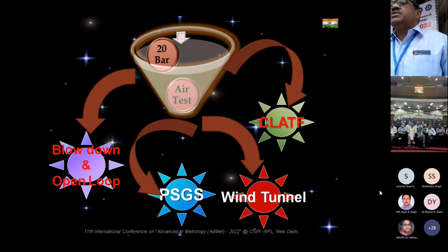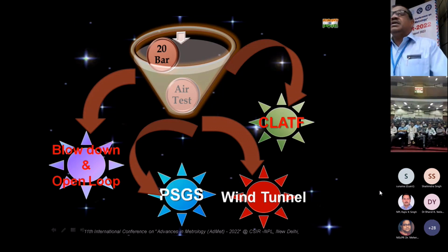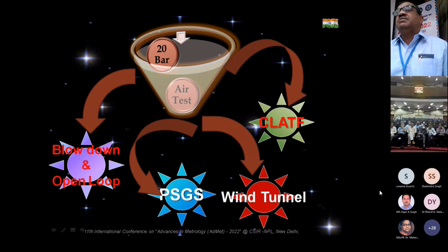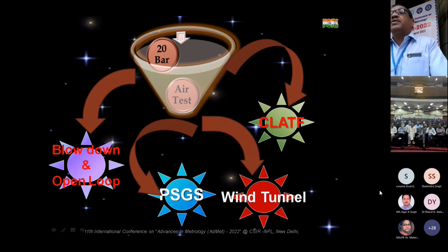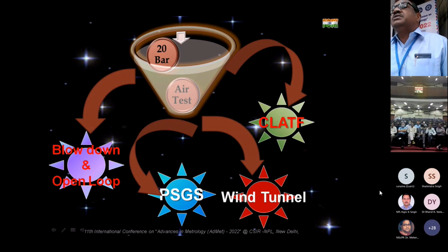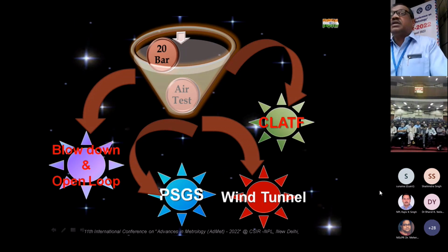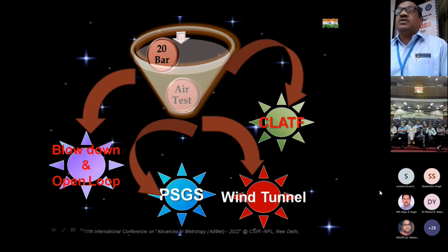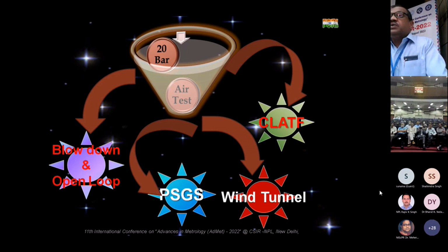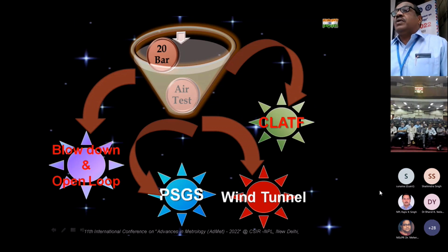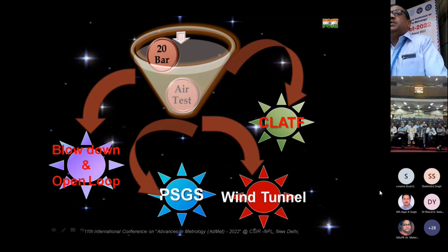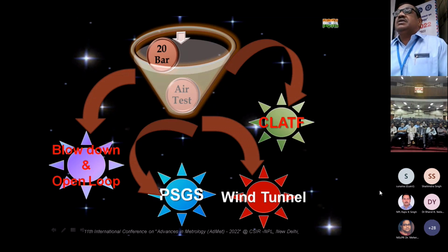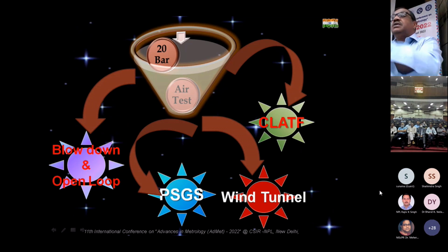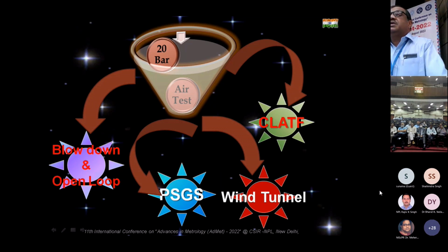I am presently heading the airflow calibration facilities of FCRI. Initially, FCRI's expertise was given by UNDP. Many foreign laboratory experts came and established this facility, and initially a few of us went to different laboratories across the world and got trained. At that time we started an airflow calibration facility at atmospheric pressure. It is in suction mode: conditioned air inside a room is sucked through the test meter, and in series we have a reference meter, and then finally it is discharged outside.